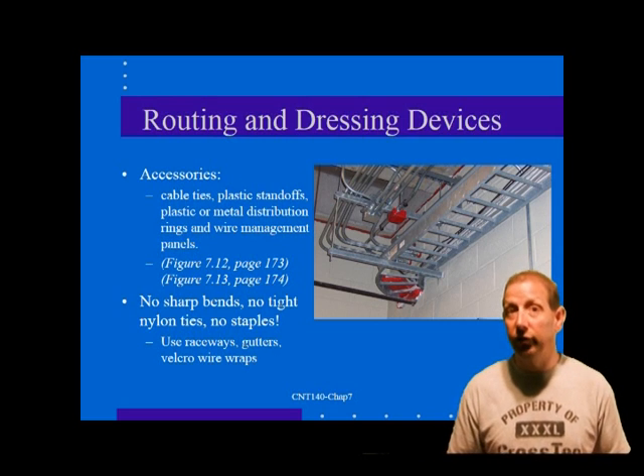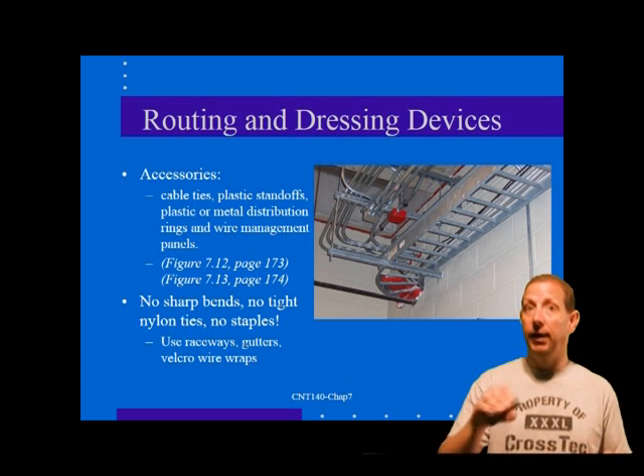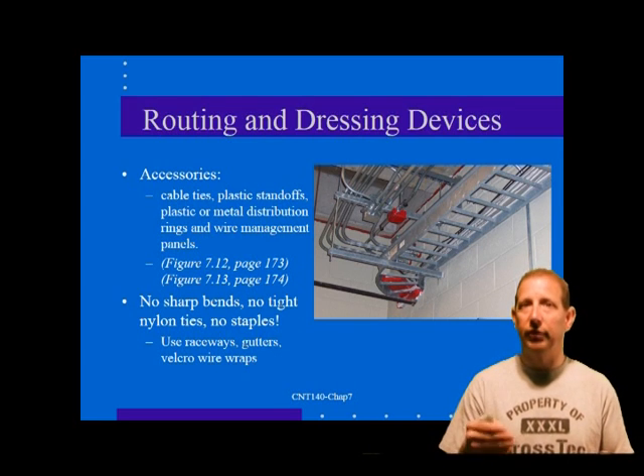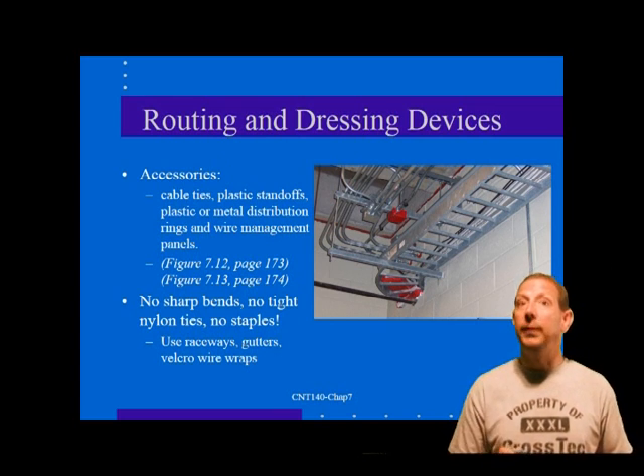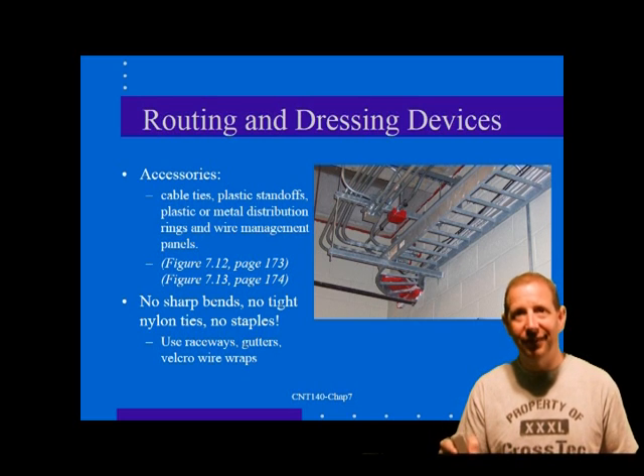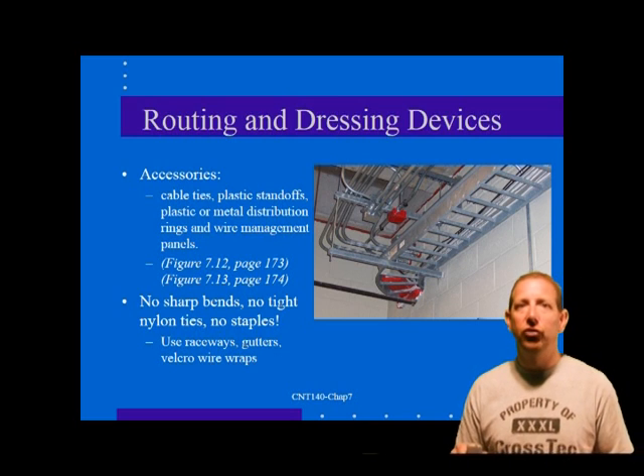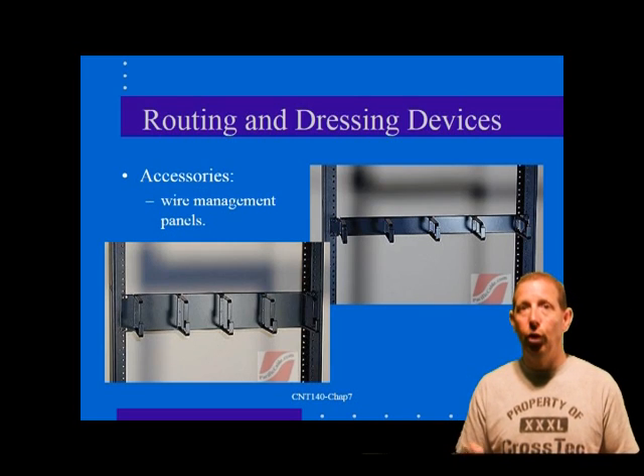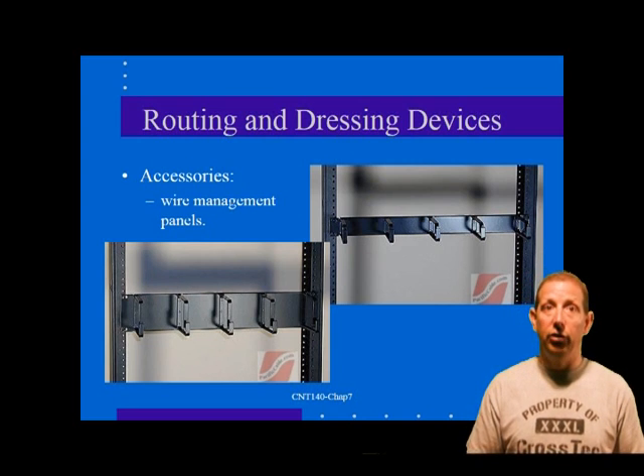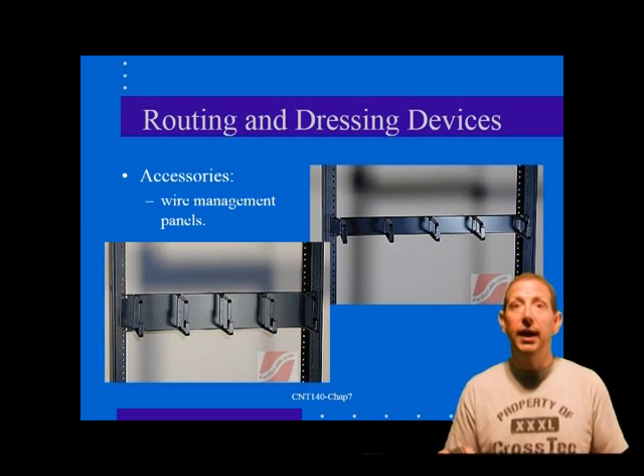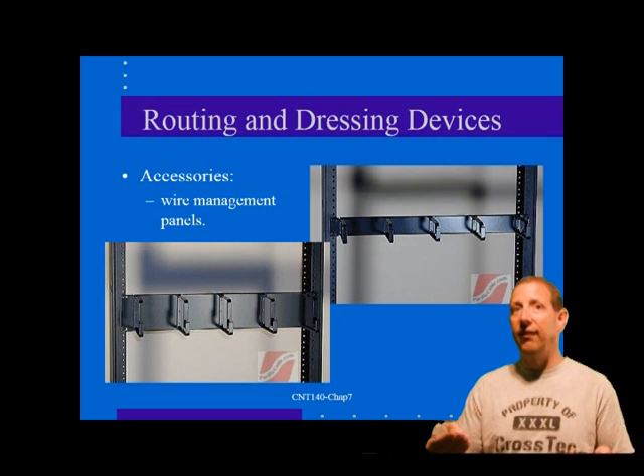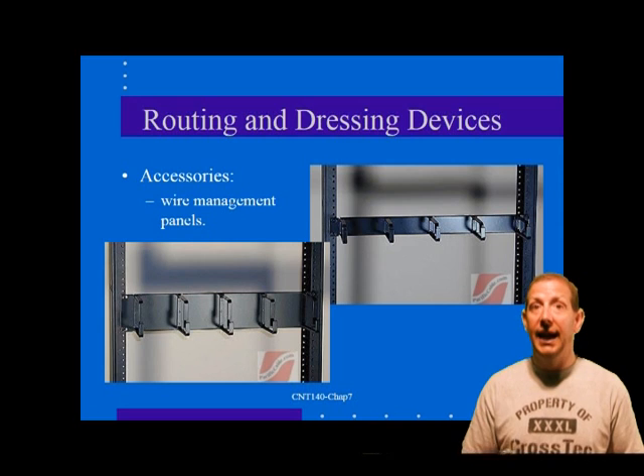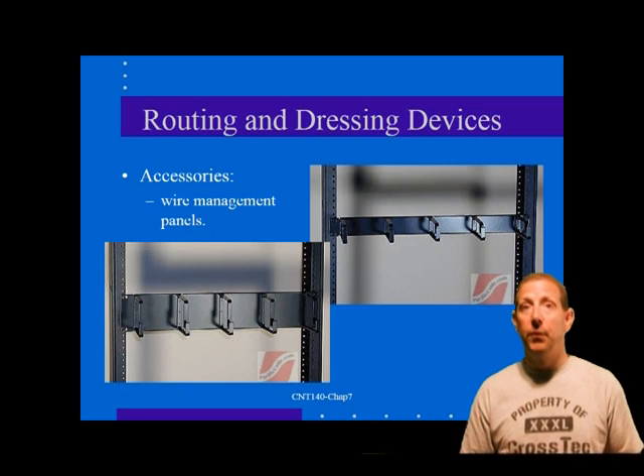There are much better ways to install your cable and cords. You should first be cautioned that using tie wraps or cable ties that are excessively tightened can cause performance problems on CAT5E and 6 wiring, and should be avoided. However, relatively loose ties that do not distort the cable jacket should be okay. The effect is cumulative, so 20 tie wraps are worse than 5. You can use a new type of tie wrap made with a hook-and-loop mesh, or Velcro type, in lieu of traditional nylon tie wraps. This new tie wrap is wider, does not pinch the cable so badly, and is also easily removable so that new cables can be added without adding tie wrap clutter.